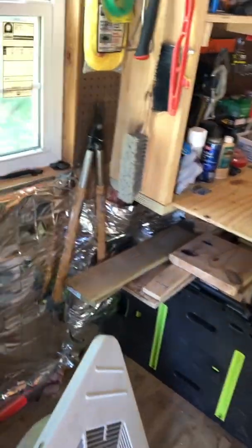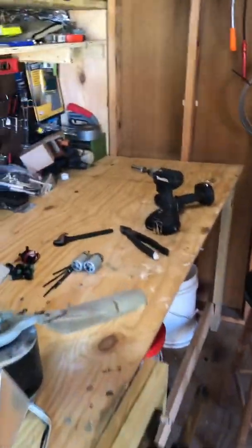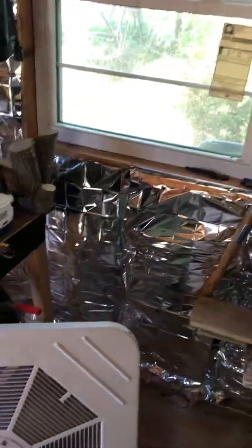Another interesting thing is that no matter how huge your exhaust fan is, if that was 10,000 CFM and it was basically like a freaking wind tunnel in here, you would still get a decent amount of cooling. This size system would be just fine. You don't cause any issues by doing that. What that will effectively do is heat the A-frame, which will heat the water, which will heat the coil, which will encourage more evaporation slightly, and so your system will actually work better depending on whatever your strongest element is. It's kind of like turning the whole principle on its head.